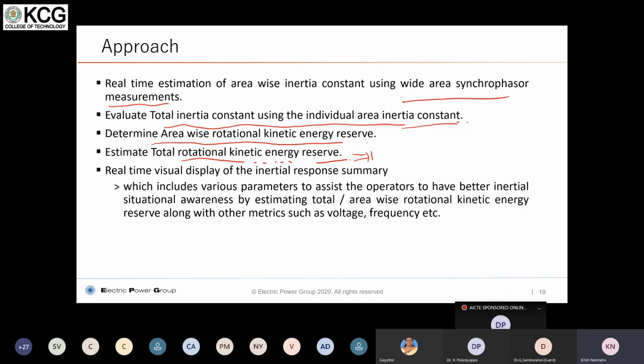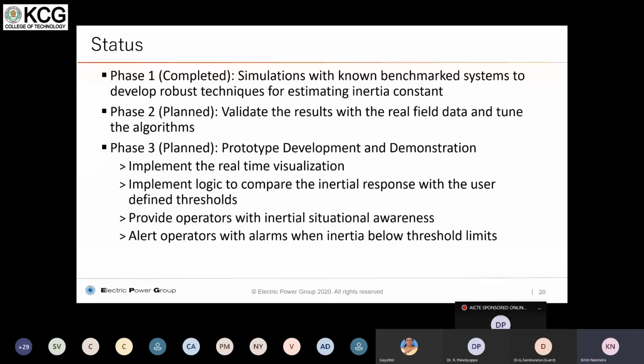So it's very important to have a real-time visual display of the inertial response summary for operators, to get an idea of what is happening in their entire grid, what amount of spinning reserves they must have, what kinds of battery backup systems they must have to support the system, and so on and so forth. These are the important outcomes of the approach of calculating the individual area and then the total inertial support for the system. Now the current project we have developed is done in 3 phases. The first phase is completed, where we have done simulations with known benchmark models to develop a robust technique for estimating inertia constant.